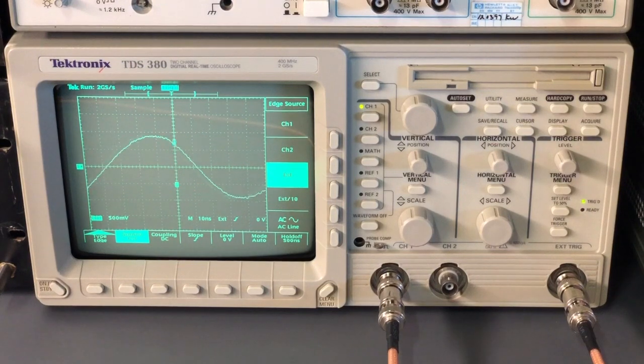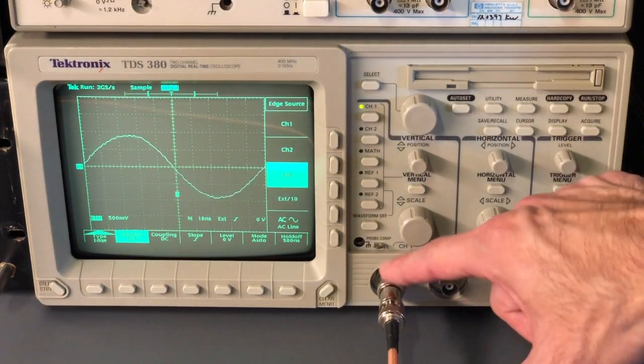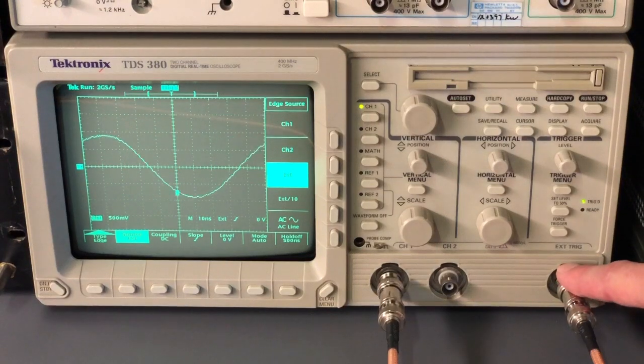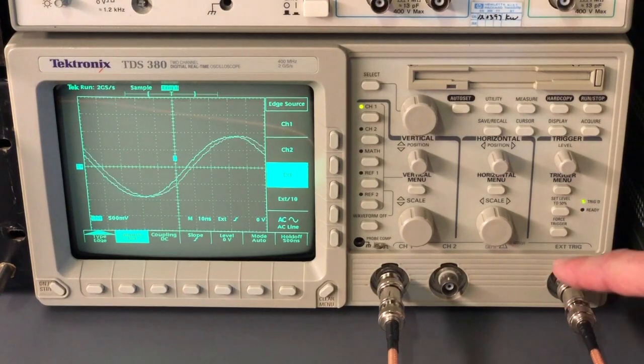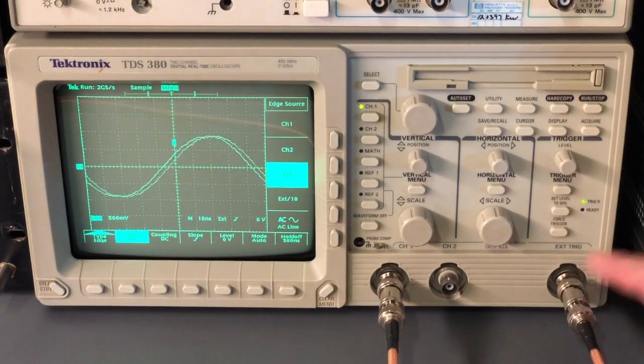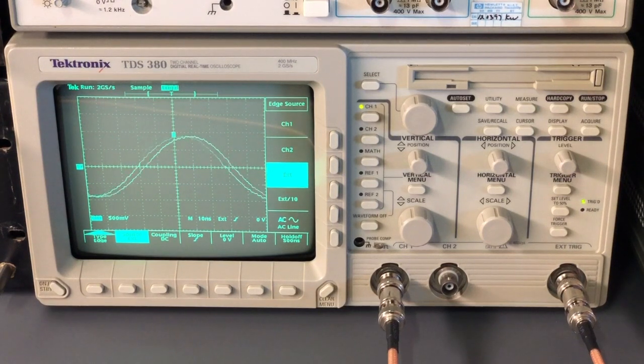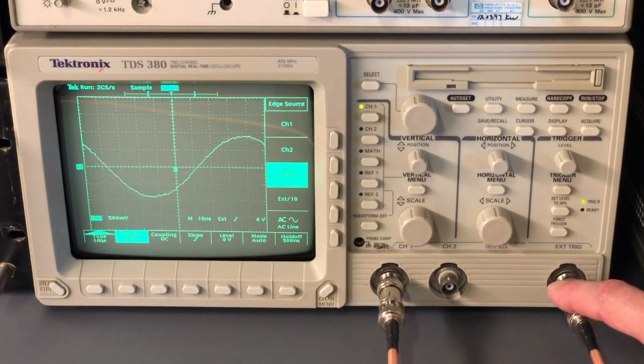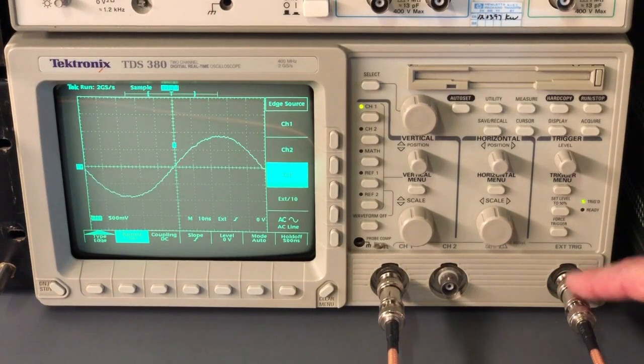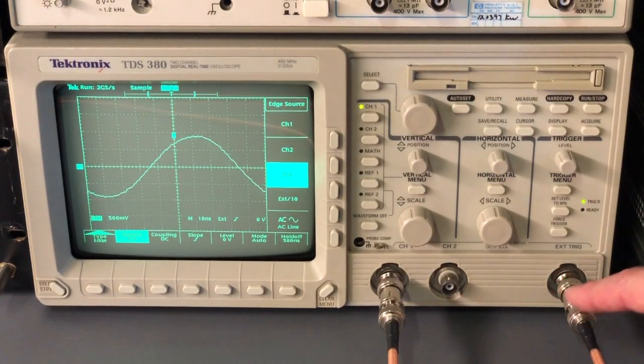Now on the oscilloscope, channel 1 again is the counter time base from the frequency counter, and again over here we have the external reference oscillator's input. Okay, this is a very high precision 10 megahertz signal coming in here. So my external reference oscillator is based on a 10 megahertz ovenized crystal oscillator that is synchronized to the GPS time signal. So by synchronizing that oscillator, and it makes minor corrections to keep it precisely at 10 megahertz, it has an accuracy on this signal of 10 megahertz plus minus 100 microhertz. So 10 megahertz plus minus 100 microhertz. Very, very precise signal coming in over here.